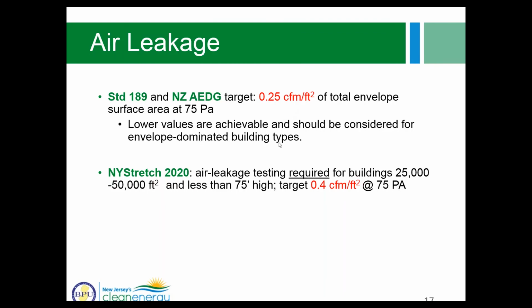And these values are generally achievable, and low values are achievable. And in fact, now there is a proposal to change 90.1 requirements from the current 0.4 CFM per square foot at 75 Pascal to 0.3 CFM per square foot, because these lower air leakage values have proven to be achievable and cost effective. But if this change passes, it would be effective as of the next edition of 90.1, which is 90.1 2022.